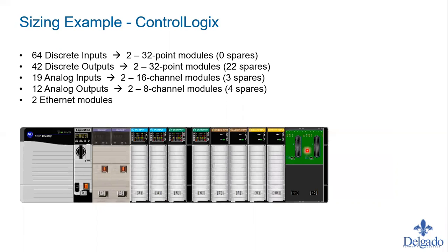You could also condense by using 32-point input modules. Before we had a 17-slot chassis; now we could bring that down to a 12-slot chassis using 32-point cards — two input cards and two output cards each handling 32 points. This reduces the physical space needed. So if you're physically constrained in your panel, this solution would be a much better fit.